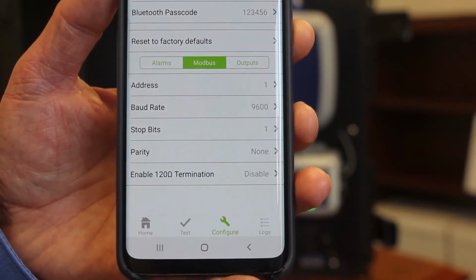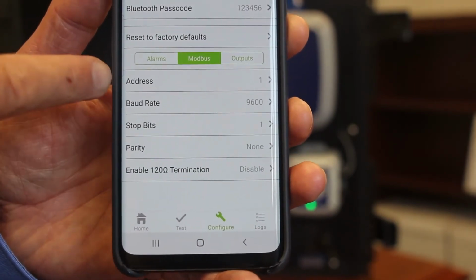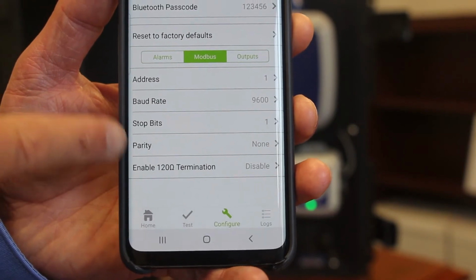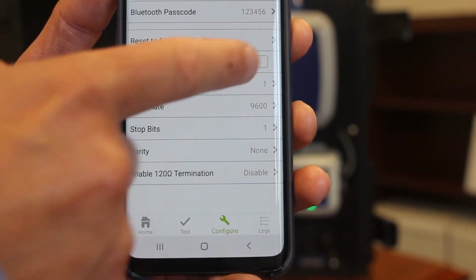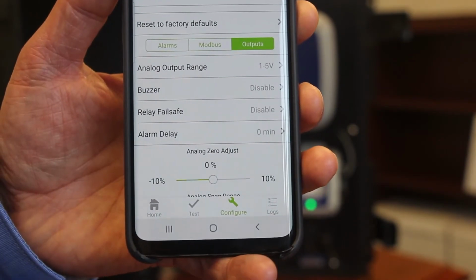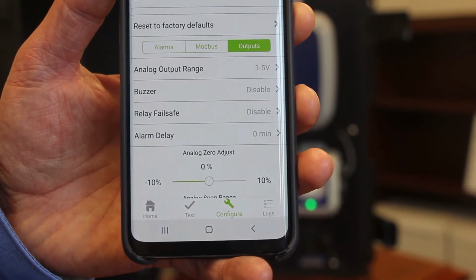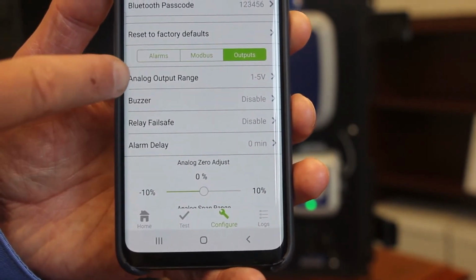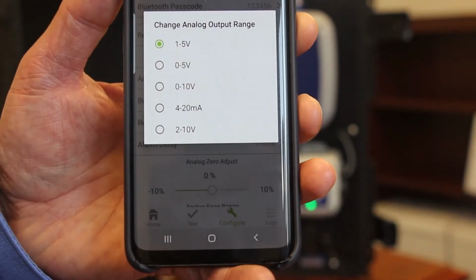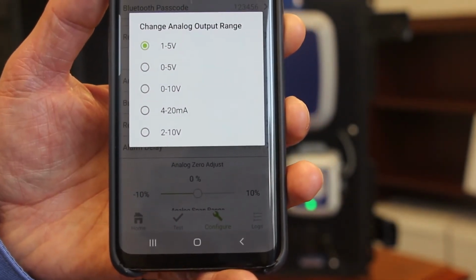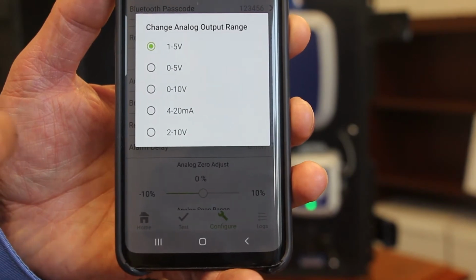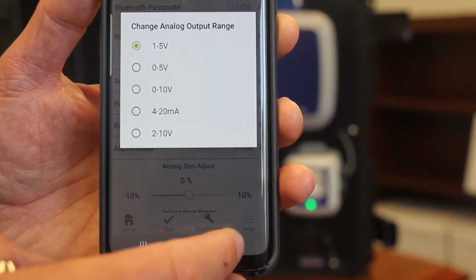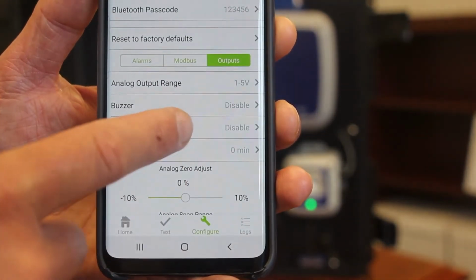In addition to the alarms on here, you can also configure your Modbus setup. So you can configure the address, the baud rates, the stop bits, and the parity, etc. You have your outputs on here. So again, you can configure your analog output range, and you can see there's a number of different options available. 1 to 5 volts, 0 to 5, 0 to 10, 4 to 20 milliamps. So it gives you some level of flexibility.